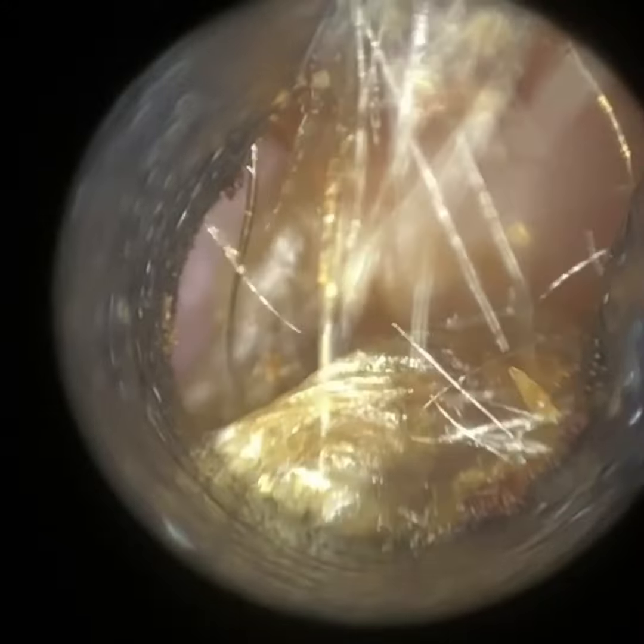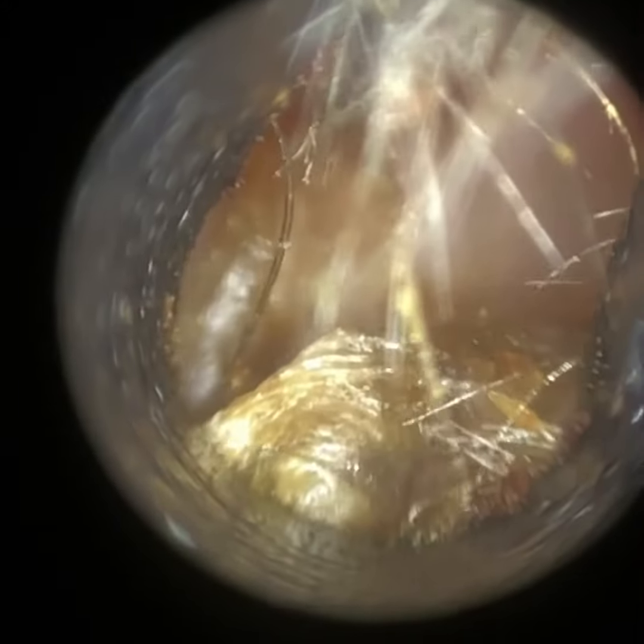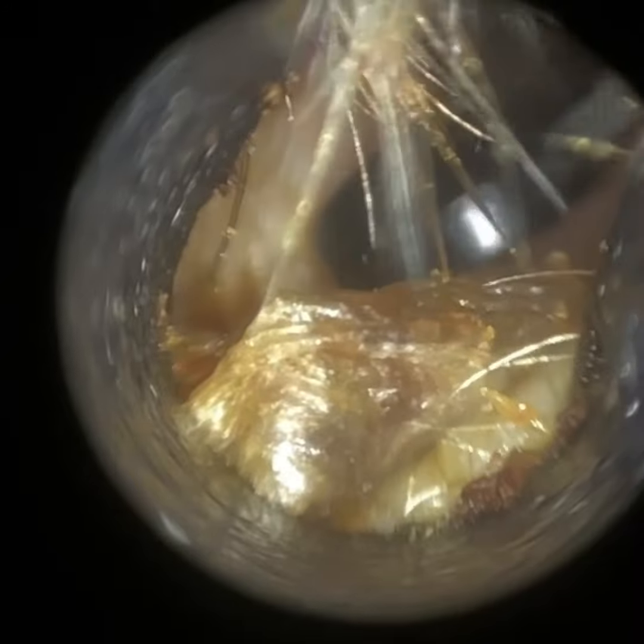In terms of the WAXscope, which is what you're seeing right now, it doesn't have the same field of view, and that's because you've got a speculum. For that reason, the field of view is somewhat negated. So what we're focusing on with the WAXscope is the zoom, the magnification and clarity. And the view you're seeing now is very akin to an ENT operating microscope, at least when removing earwax. When an ENT doctor, for example, uses an ENT microscope, this is the kind of view they receive. I've just removed a plug of wax, just a bit of keratin at the entrance. I'm just going to remove this with a Jobson Horne.